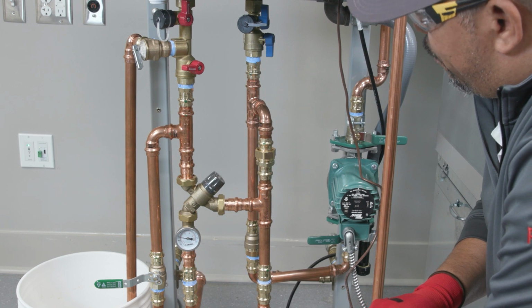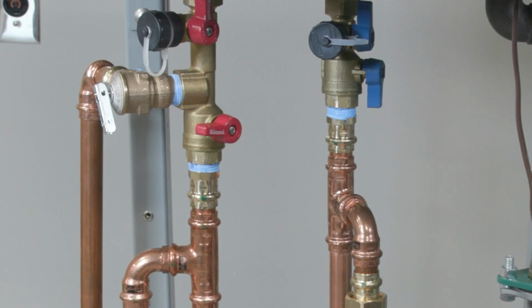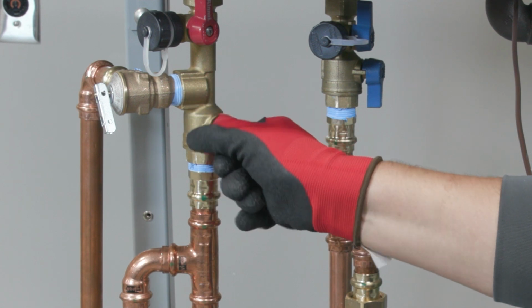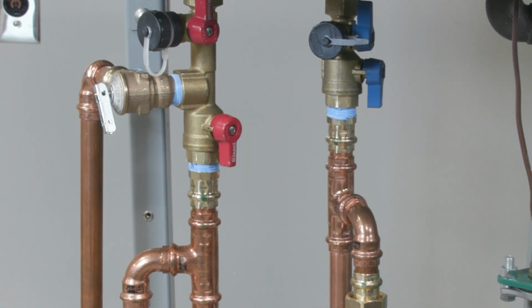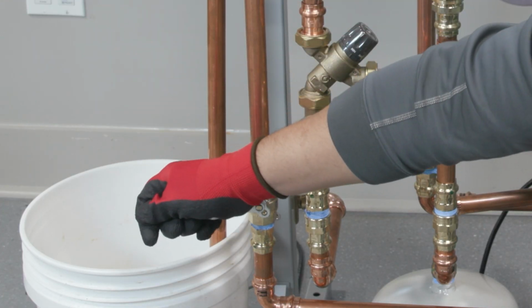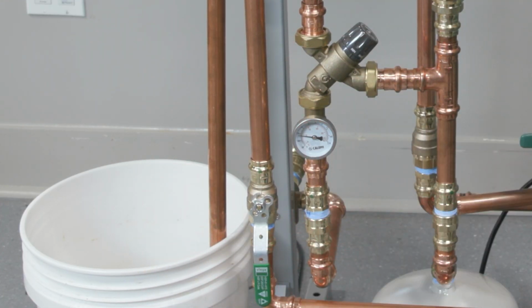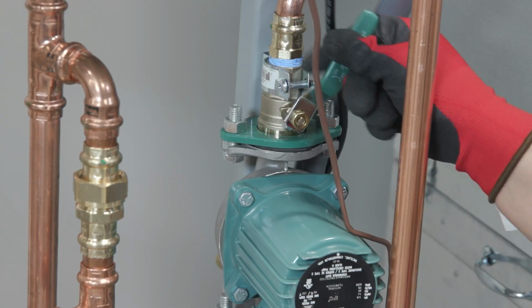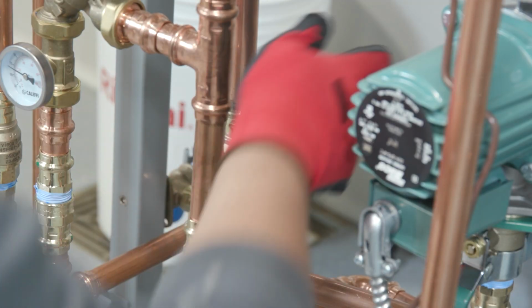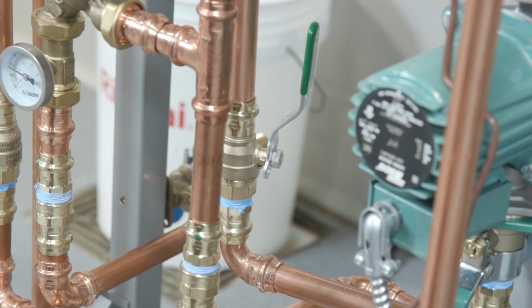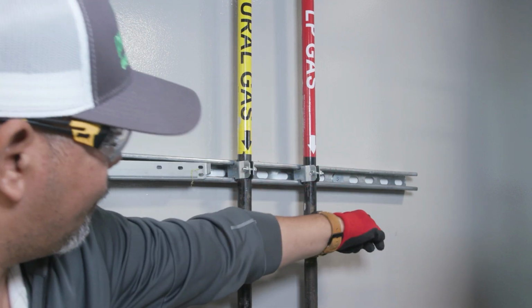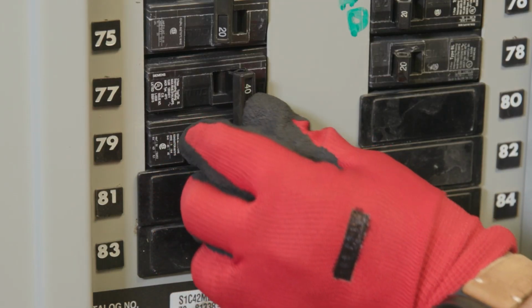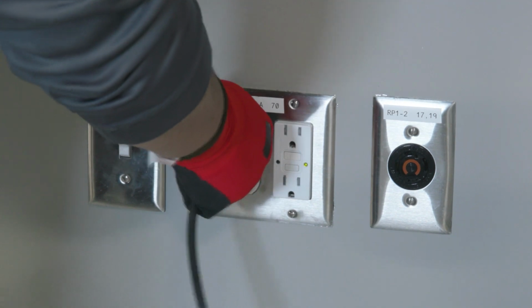Open the cold water isolation valve. Pause while you listen and look for leaks. Open the hot water isolation valve. Again, pause while you listen and look for leaks. You'll do the same for the ball valve fixture that feeds the air handler: the isolation valve above the pump, the isolation valve below the pump, and the valve from the air handler to the water heater return. Open the main gas valve. Restore the electrical power to the air handler and the tankless water heater.